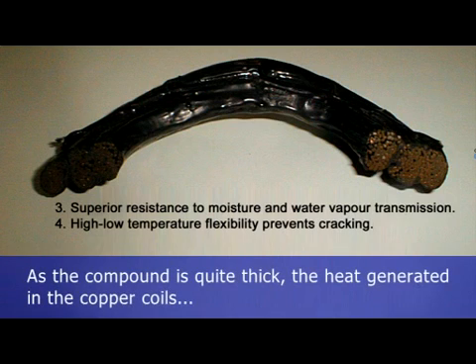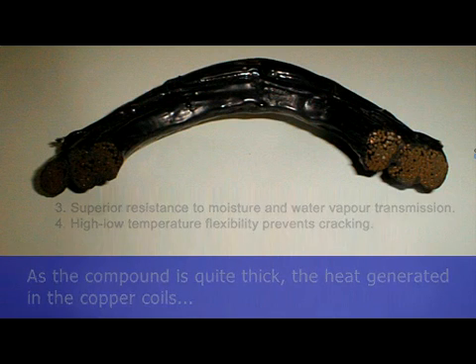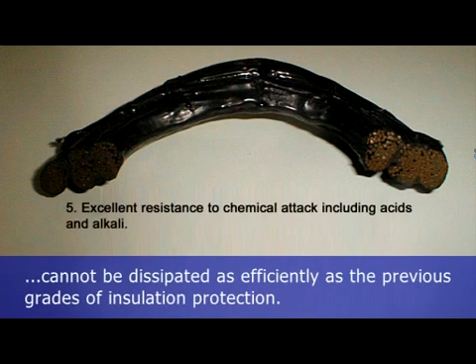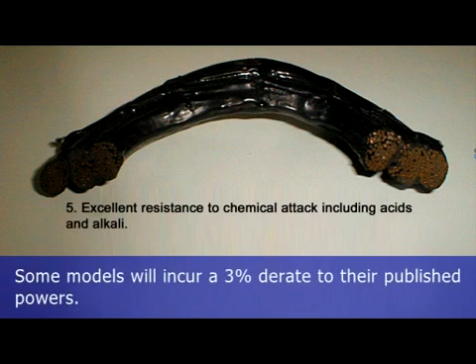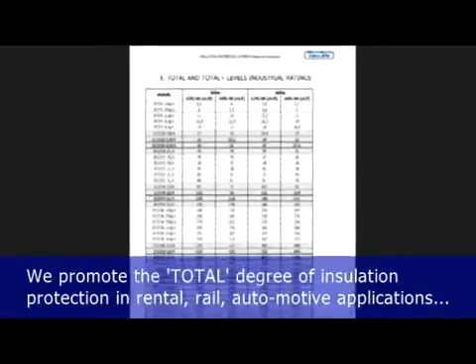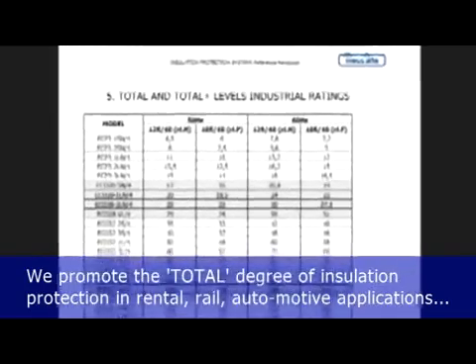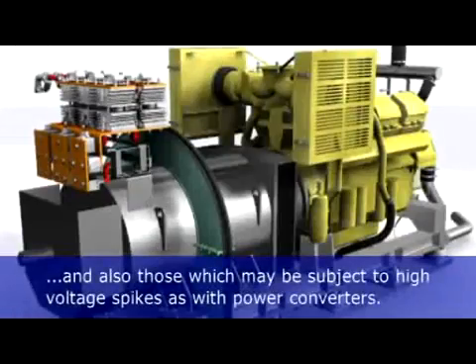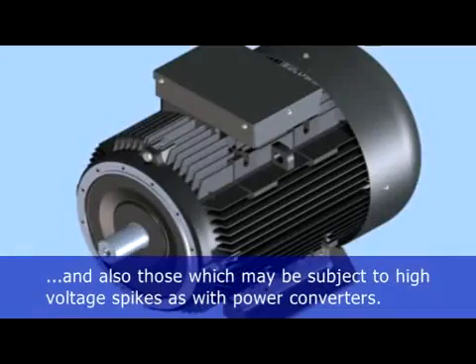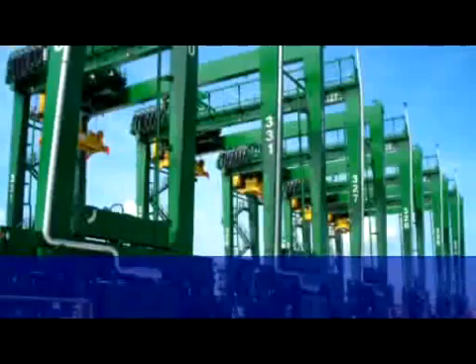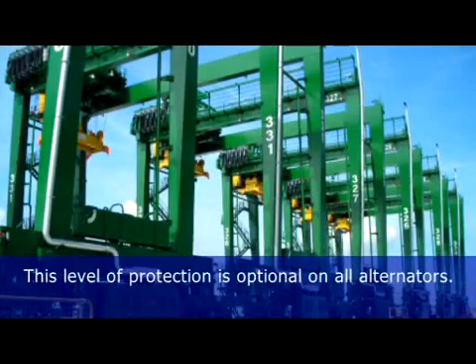As the compound is quite thick, the heat generated in the copper coils cannot be dissipated as efficiently as the previous grades of insulation protection. Some models will incur a 3% derate to their published powers. We promote the total degree of insulation protection in rental, rail, automotive applications, and also those which may be subject to high voltage spikes, as with power converters. This level of protection is optional on all alternators.